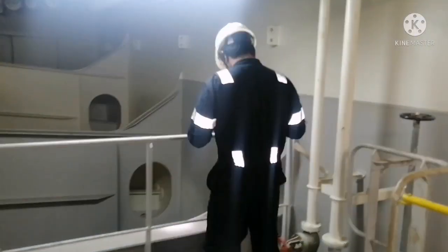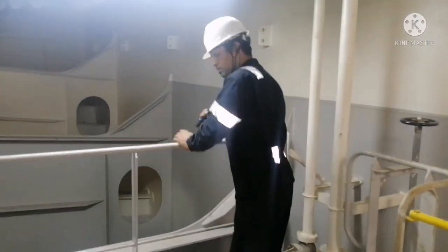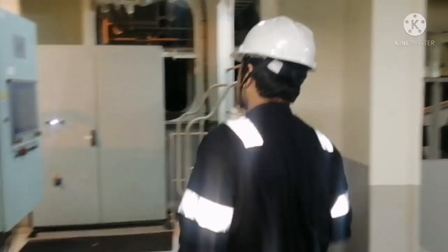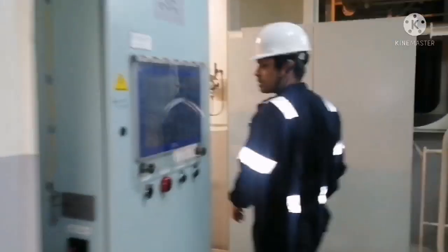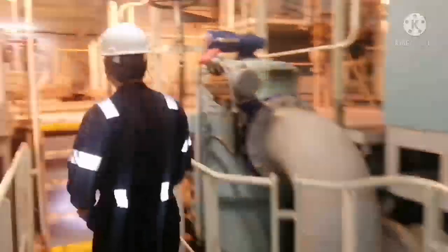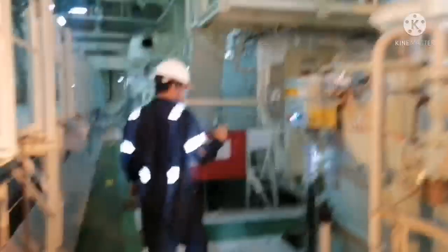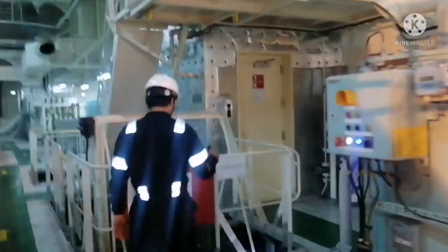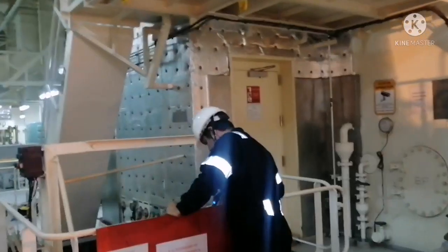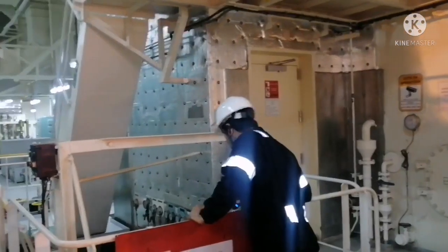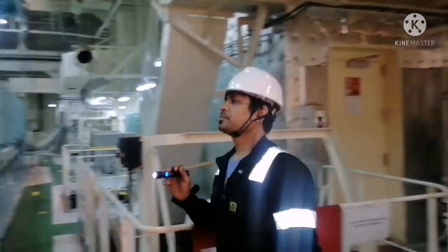On the bottom platform you have to take a proper visual inspection, because most of the seawater lines, seawater pipelines are there on the bottom platform. So you have to check properly for any leakages or something. This is your oily water separator. Just check for any abnormal leakages. None found.